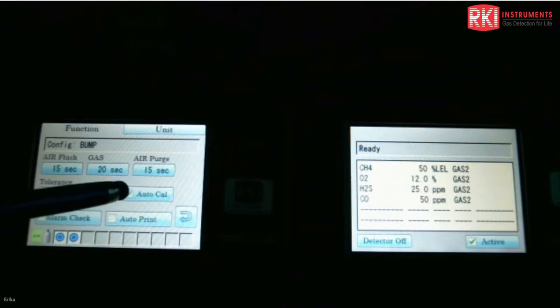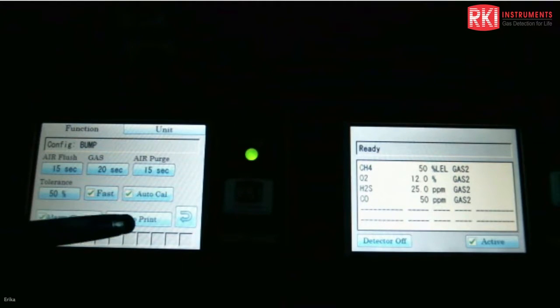Another thing you can check is an auto cal. So if it fails a bump test, it's going to go directly to calibration. There's also an alarm check setting here that you can check and uncheck, and also an auto print. The alarm check means that after the bump test, it's going to sound the alarms and light the alarms and check if everything's good. And it's going to give you a pass or a fail. Auto print would mean it's just going to print whatever results it has for that bump test. So that is pretty much it for the bump test.